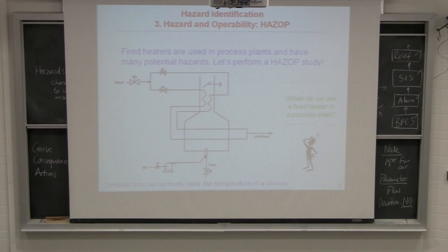Okay, so if you were looking at the deviation of low flow of air, that would be the formation of carbon monoxide. Okay, so actions to take. Okay, so if there's no flow of air, we have an interlock to shut fuel. So, again, those few lines of PLC code, detect a minimum amount of air flow. If that's not met, shut down the fuel flow. Other suggestions? Ensure that valve fails open. Ensure the valve, the air valve fails open.